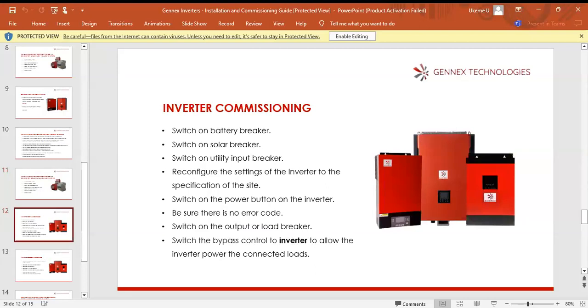Inverter commissioning now. This is the procedure, and it's also very important. The battery breaker is the first thing you do. Of course, as you are installing, all your breakers should be in the off state. When you want to start commissioning, you start from the battery breaker. After you have confirmed your installation is okay, then switch on the solar breaker, which is the next one. When you switch on the solar breaker, the inverter wakes up, displays on the screen and immediately starts charging. If solar is not available, switch on your utility, which could be your generator or public supply. Immediately you do that, the inverter wakes up and starts charging.